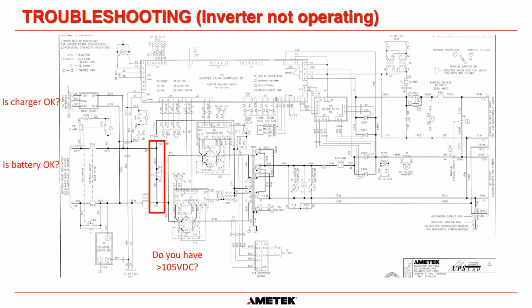Or it could be, is the charger okay? You know, the charger should be taking AC and turning it into DC. So we need to make sure that the output of the charger is DC. And remember, always remember, whenever you have a charger and a battery, the output of the charger is in parallel with the battery. So the only way that you can tell if this charger is working is to open the battery disconnect and make sure we still have 135 volts DC going into the system, because that's what it should be roughly to keep a lead acid battery charged and for the inverter bridge to run. So that's the first thing you need to do.